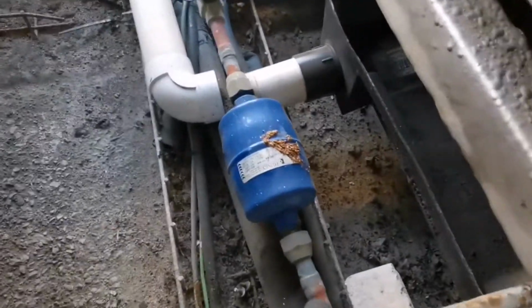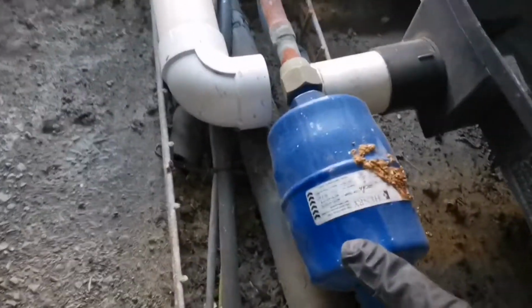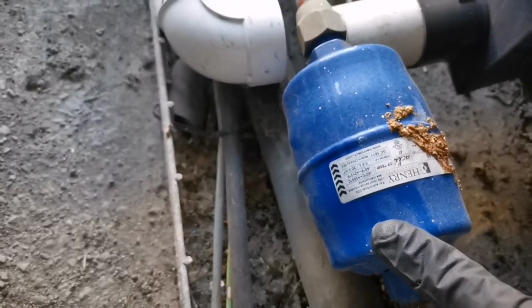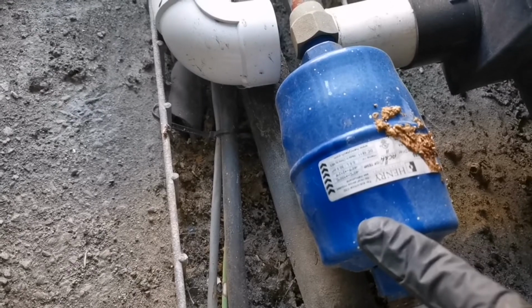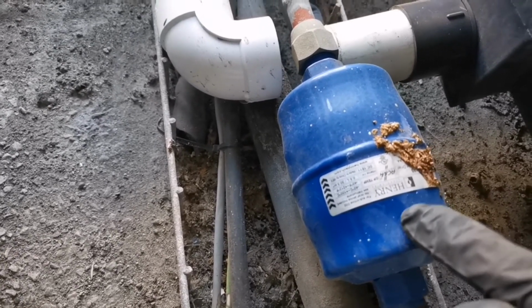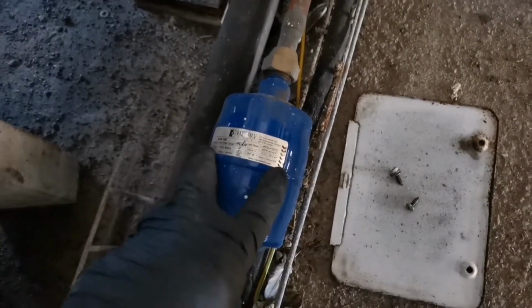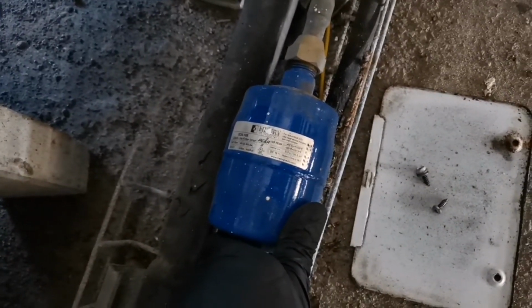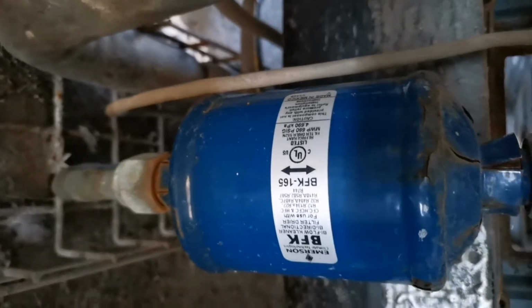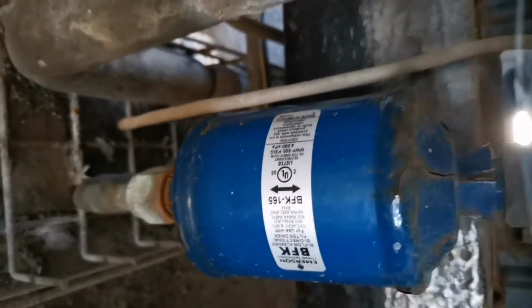But so far, yeah. And let me show you guys the other big issue that I found. Look at that. That is a single direction valve or filter dryer on the liquid line of a heat pump. And this is the slave condenser, exact same one. Alright. So what you want is that right there. You got flow in both directions.